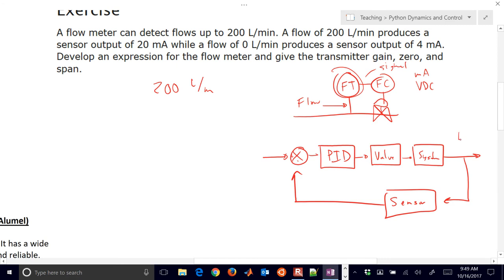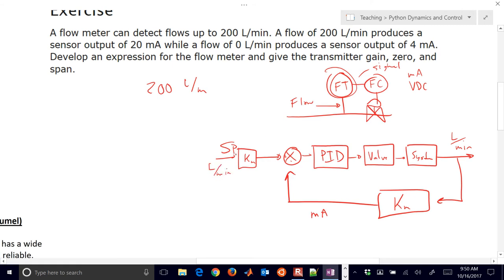And this is our sensor right down here that converts this signal into a sensor. So for example, in this case, this might be liters per minute. And then it's going to convert it into a milliamp signal. And so the set point that we give it, we're actually going to want to convert the set point into a certain gain here. It's going to be a gain between the, I'll put KM there. That's going to be our gain between what we measure and the signal that it outputs. So the set point, this might be in liters per minute. And it's going to convert that into a corresponding milliamp signal. And then the error that we have between the set point and the PV. This is our PV, a process variable right here. The error is also going to be, might be in milliamps, for example. And then the PID controller may send, for example, a PSIG signal to the valve. And then the valve is going to open or shut.